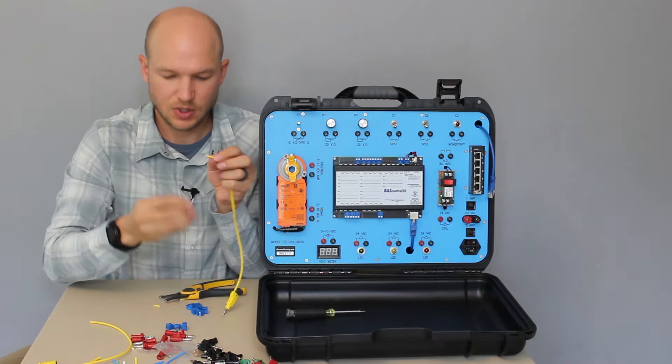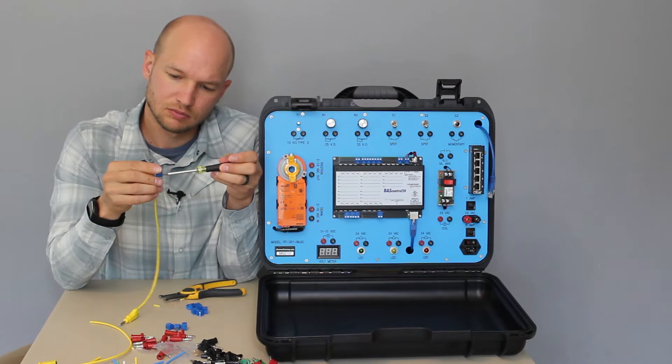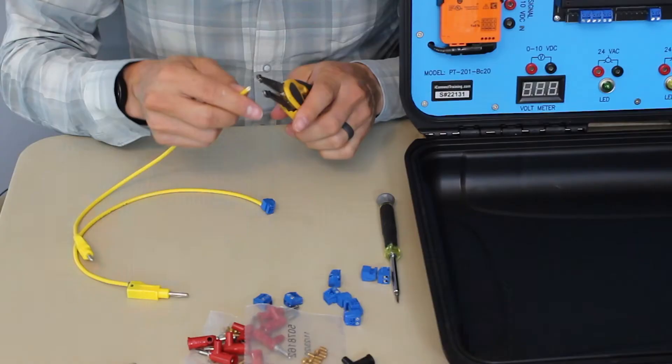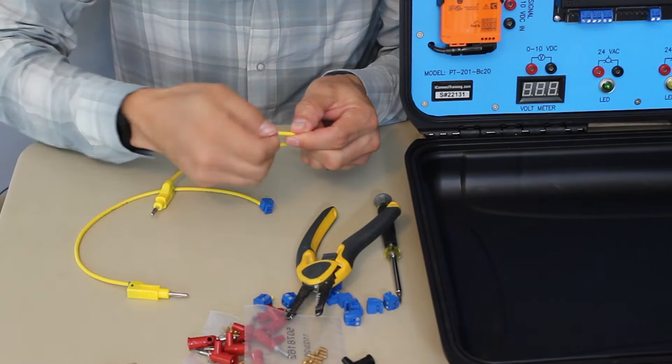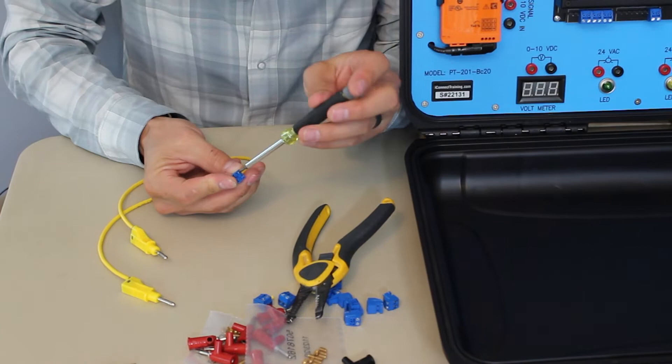So we're going to take one of our leads and strip roughly an eighth inch, maybe a quarter inch, to go into the connector. We're going to twist the wire, get it a little bit tighter, put it into the connector and then tighten it. So I'll zoom in so you can see that a little bit closer. So again, we're going to strip roughly an eighth inch off, tighten the wire by twisting it, putting it into the connector and tightening.